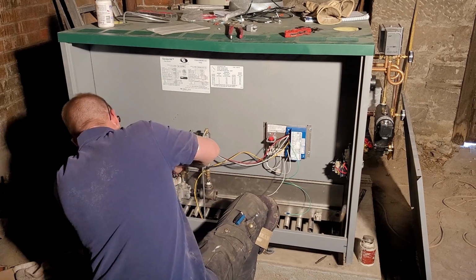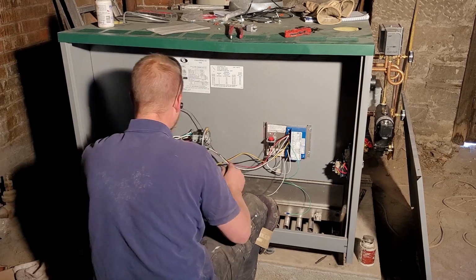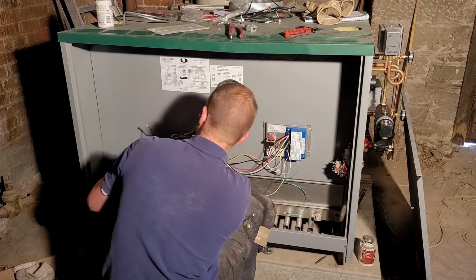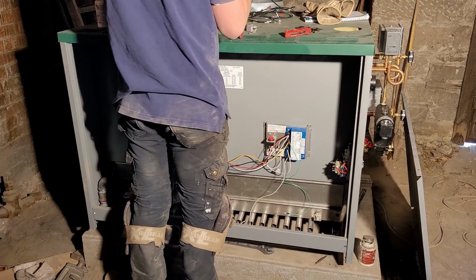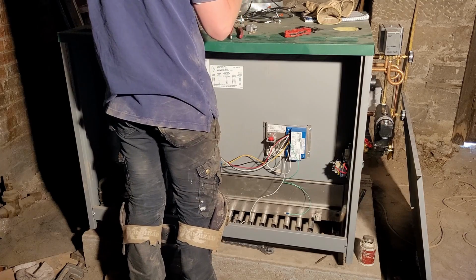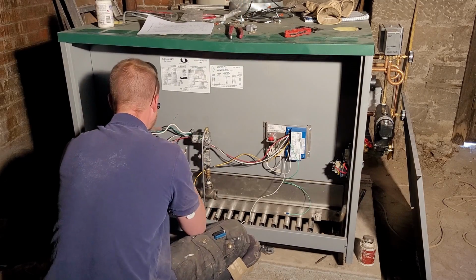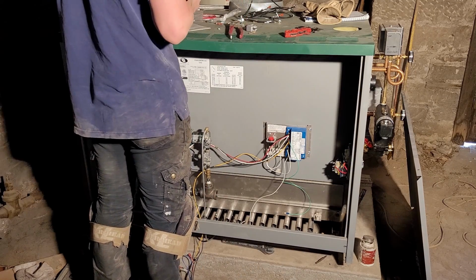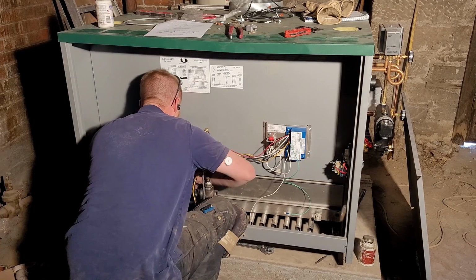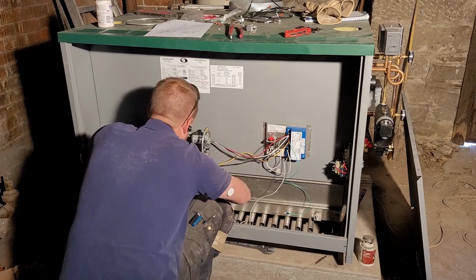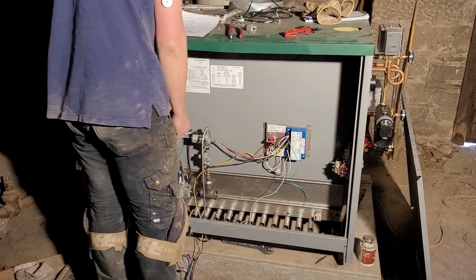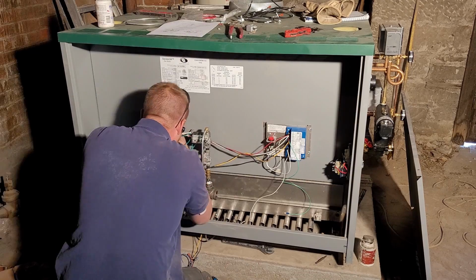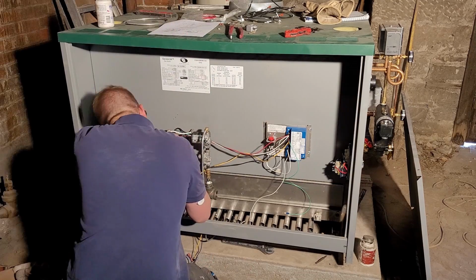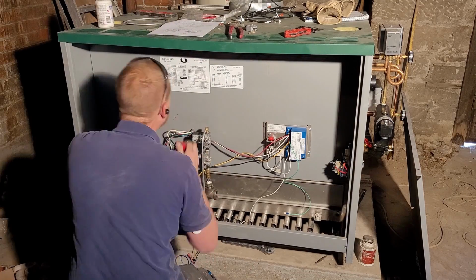So another aspect of safety here. Now we have four safeties: the ignition module manual reset. We have the flame rollout switch that, if it tripped, would have to be replaced. We have the manual reset low water cutoff that we discussed in the previous video. We have the manual reset pressure control, also in the previous video. All of these things have to be working correctly for the boiler to even fire.